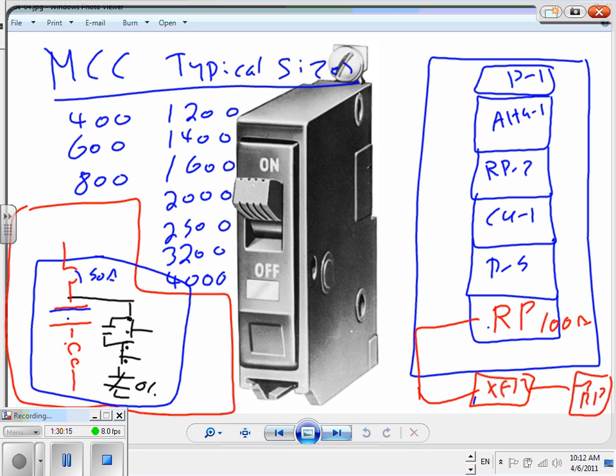Any question, guys, about the panel? So that's basically what we, for those of us who are electricians, you guys know that you can't land 2 cables under 1 lug unless the lug is rated for 2 cables. That becomes more installation. So if I have 2 cables and I want to land them on a circuit breaker, I need 2 lugs, 1 lug for each cable.